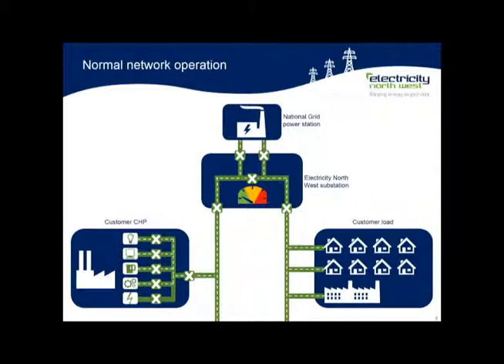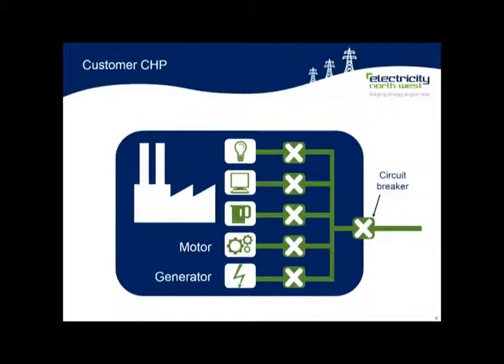This is a large customer and it has its own private electrical network designed to supply lighting, heating and other general usages around the site. It also has a large motor and a combined heat and power generator or CHP unit. This unit can supply electricity both for the customer and it may also export electricity back onto our network. We have shown each part of the customer's network protected by a circuit breaker or similar device.